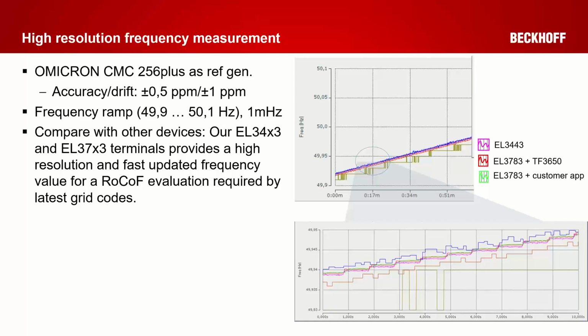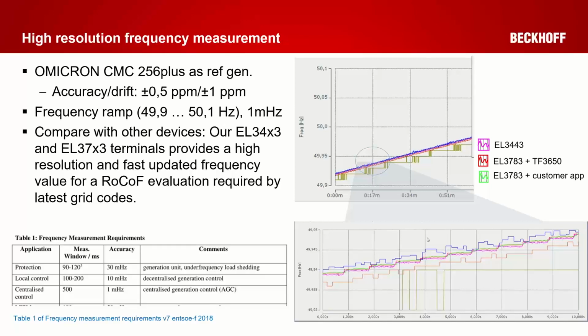And this is the basis of a good and fast enough rate of change of frequency evaluation required by the latest grid codes. Looking in the wide range of internet documents, I find a document from the European Network of Transmission System Operators. This is almost the master of everything. And here I find a table, and inside this table it shows that for decentralized generation control, and this might be our wind turbine, at minimum we should have a resolution of 10 millihertz, and also for the ROCOF of 10 millihertz per second. But for centralized generation control, this is our wind power control, we should already have a 1 millihertz resolution. And based on this requirement, I can say that we can meet these requirements with our terminals.